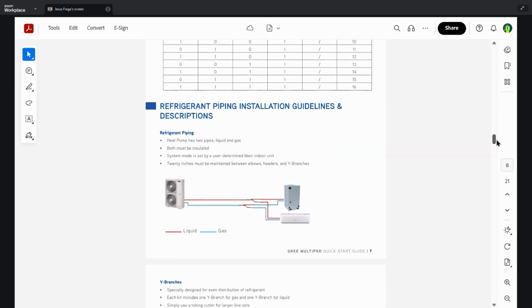All right, moving on. Refrigerant piping installation guidelines and descriptions. This heat pump has two pipes, liquid and gas. Both must be insulated. System mode is set by the user to determine the main indoor unit, or is selected randomly by the system if you do automatic addressing. A lot of these same things apply, so we know that 20 inches must be maintained between elbows, headers, and Y branches. And here's an example of how those Y branches are laid out.